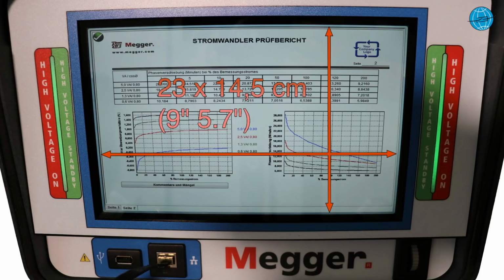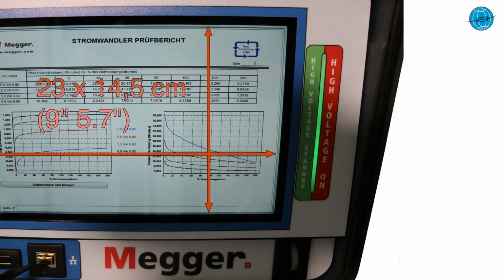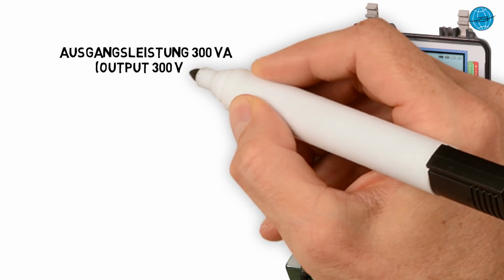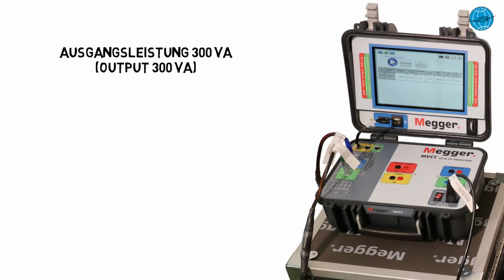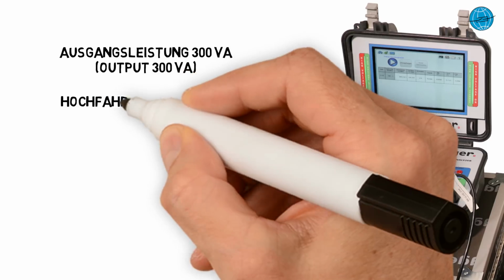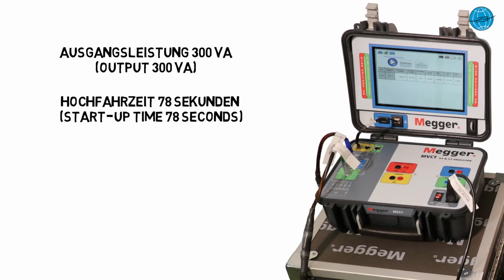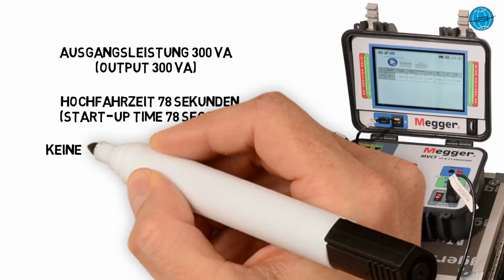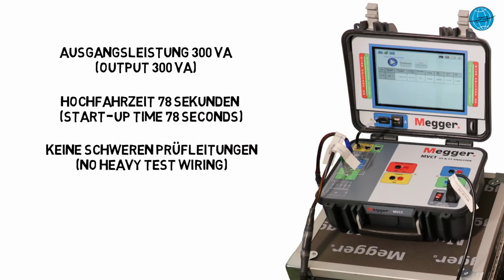The MVCT can also be configured to be delivered without the display or operated via a laptop using MEGGER's software PowerDB or MEGGER's proprietary Smart Touch View interface. The maximum output power of the MVCT is 300 VA effective, and the startup time of the Windows-based system after switch on was 78 seconds in our test. Since the MVCT works on the secondary side, no heavy cables are required here either.